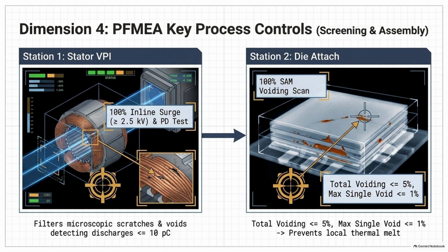If there is a tiny air bubble in the insulating resin or a microscopic scratch on the enamel wire coating, that 2.5 kilovolt pulse will jump that gap. It won't be a full short circuit, just a tiny localized spark. The testing equipment is sensitive enough to catch electrical leakage as small as 10 picocoulombs. Picocoulombs. Yes. We are talking about detecting the movement of almost individual clusters of electrons.